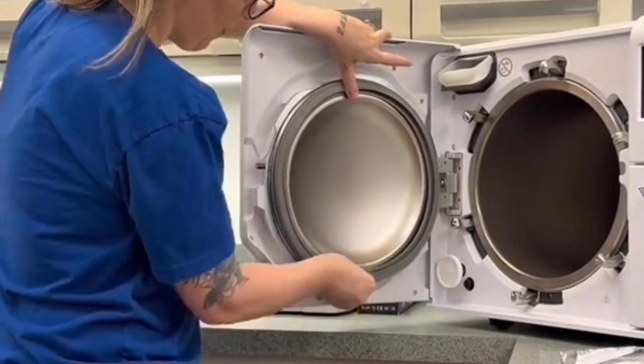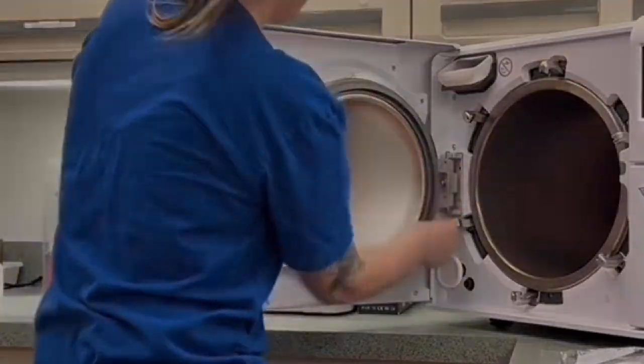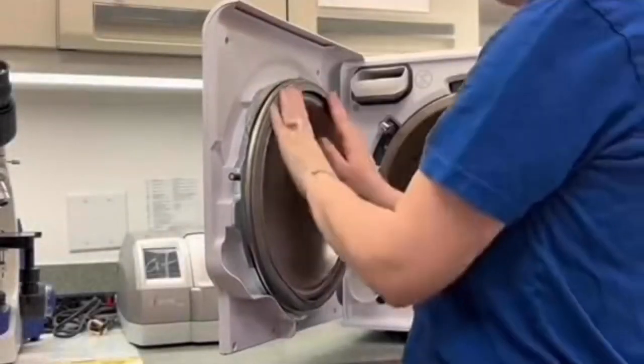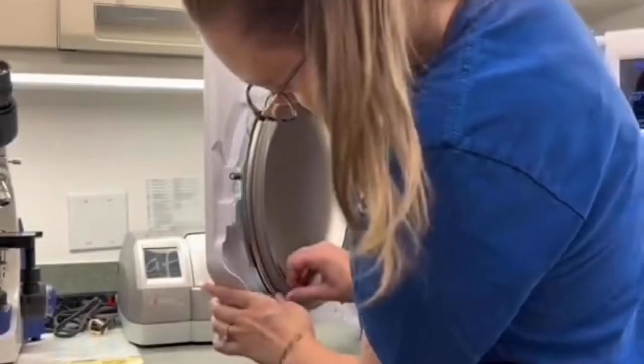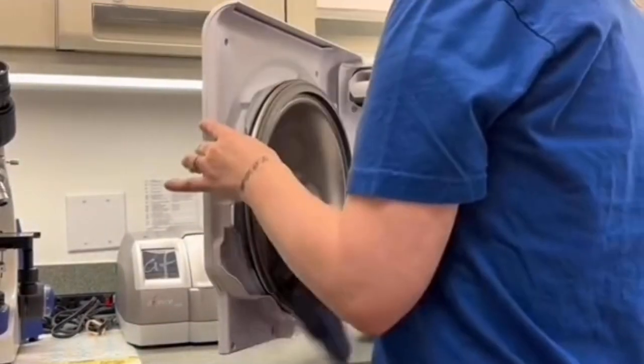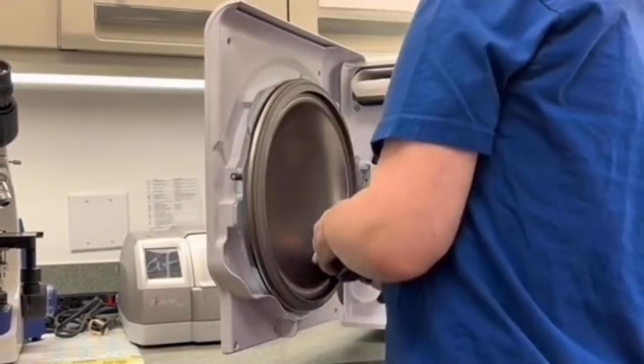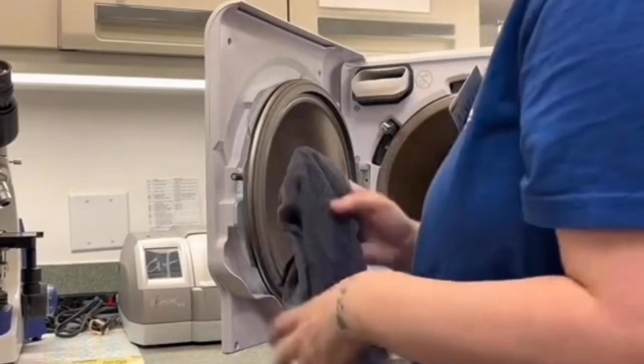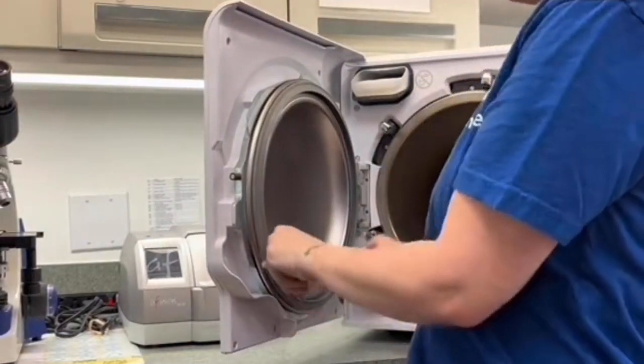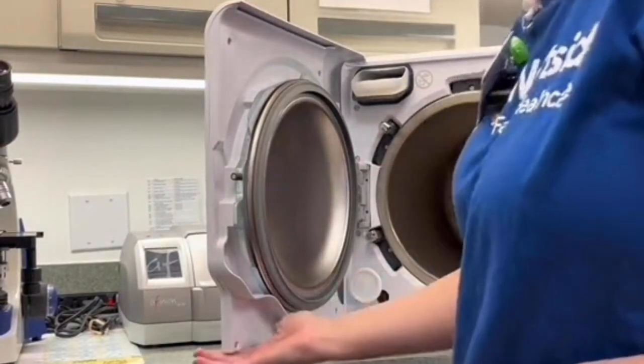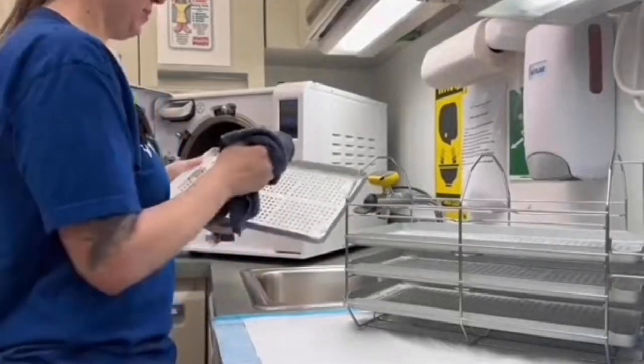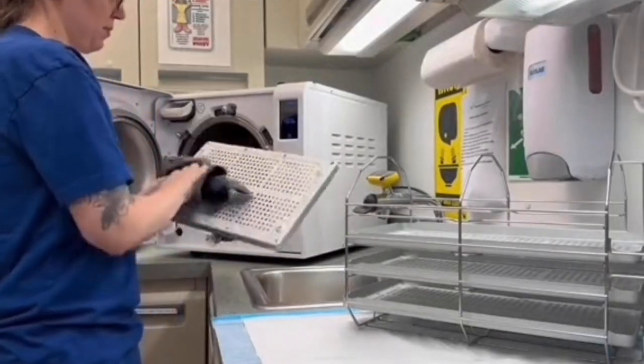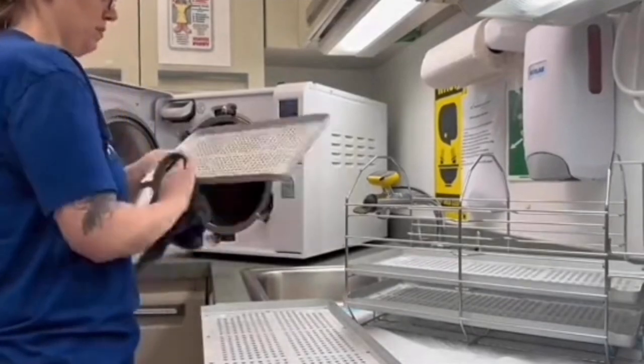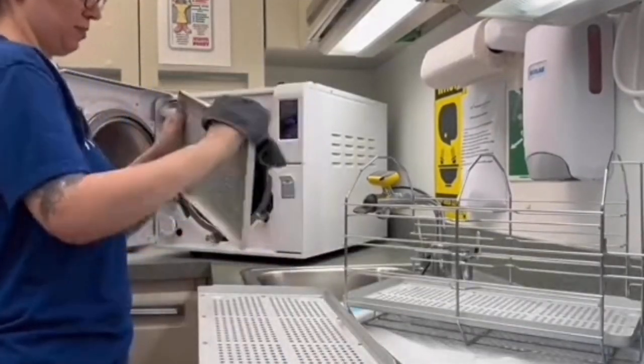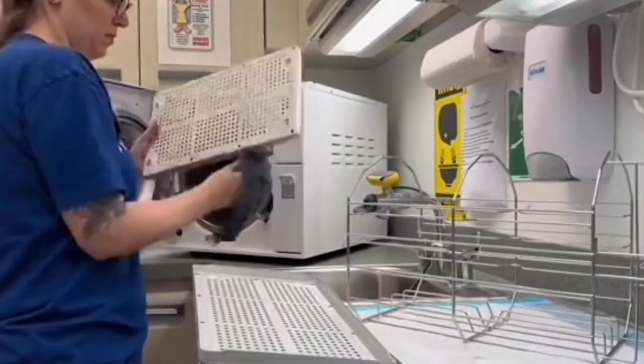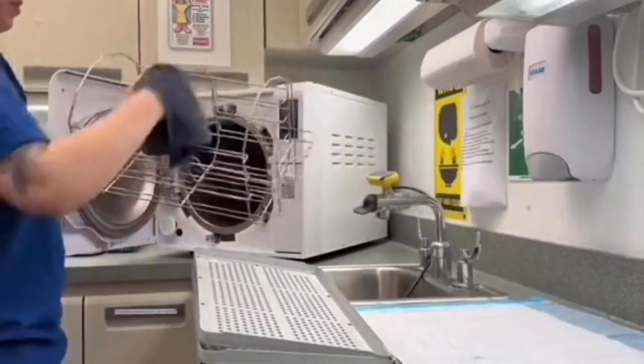You will feel it pop in place when done right. Take a moment to feel around the entire gasket to make sure it is correctly in place. If it's not, start again. The gasket must be properly placed or the autoclave will not sterilize correctly. Wipe down the rack and put it back in place. Remember, you will hear it click when it is in place. Wipe down the trays and place them back on the rack.